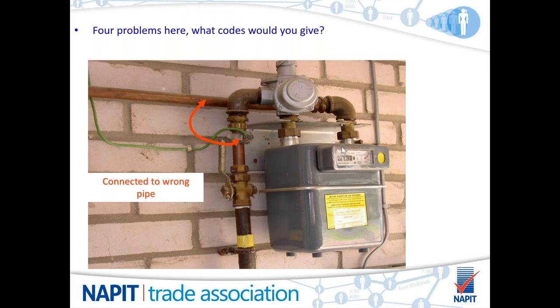Personally, the best way of working on it, to me, would be to do a continuity test between the two pipes. If you've got zero ohms between the incoming service and the installation pipe, there's a connection there. At the most, in my opinion, C3. Also, in my opinion, it's a quick job just to swap that from one pipe to another.